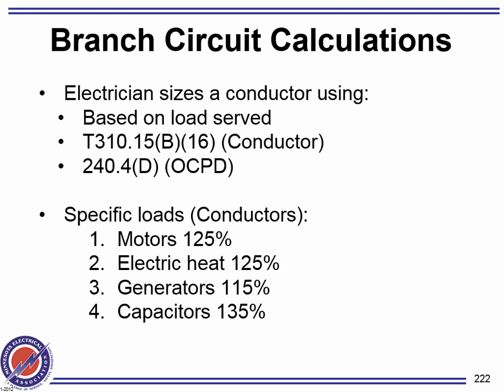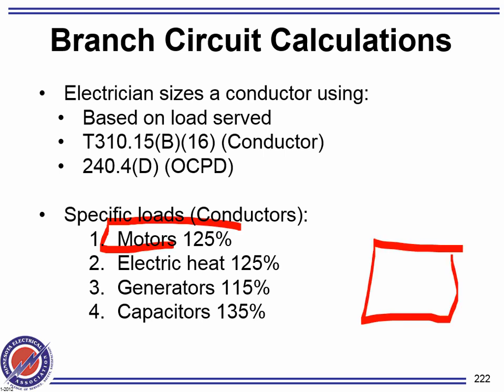Okay. So we'll take a couple of things. The conductor size. So the rule is, here's the rule. Here's my machine. Here's my overcurrent protection device for my machine. This is a 10 amp. If the load is non-continuous, all you have to do is put 10 amps worth of cable here and 10 amps worth of breaker or fuse here. You're done. Now once this is continuous.